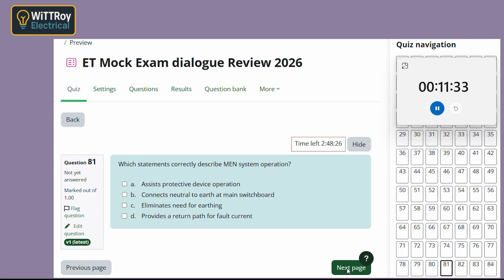Neutral is connected to Earth at the main switchboard. Yeah, that's right. Let's just talk it through a bit. The idea of MEN is to link neutral and Earth at one point, usually the main switchboard. So they're connected there, but not everywhere. Exactly, just at that main point.